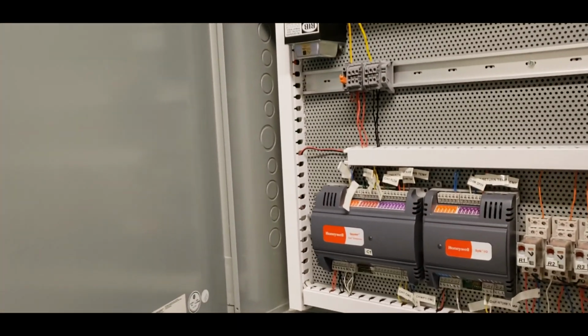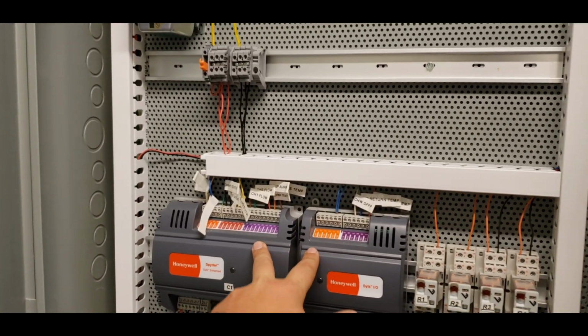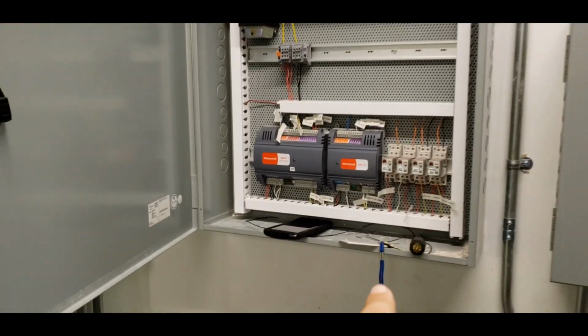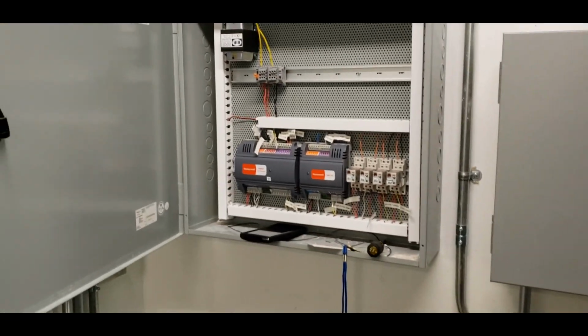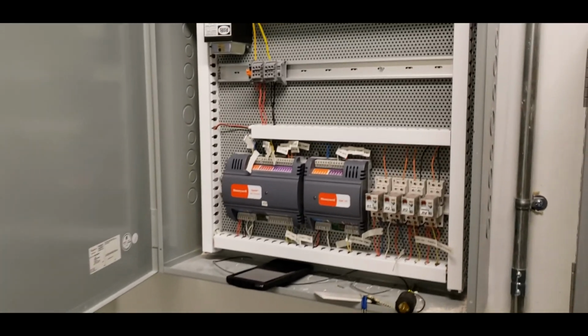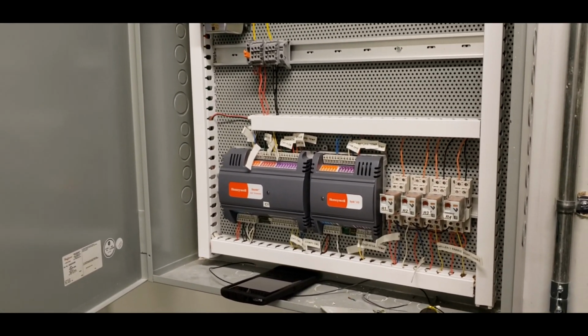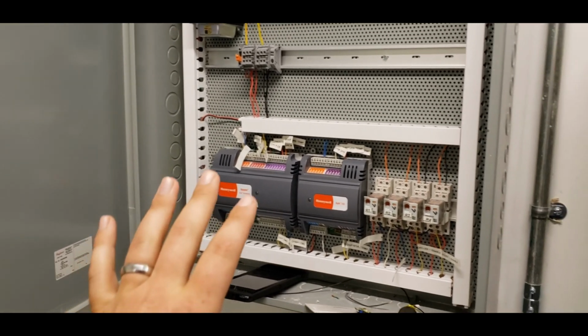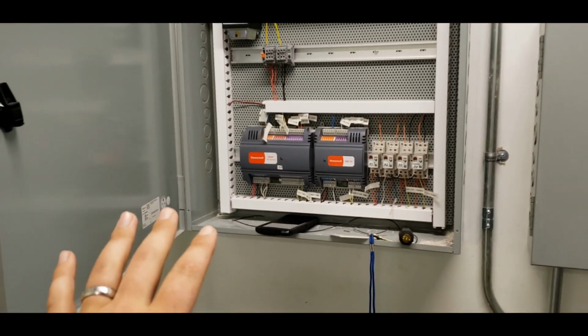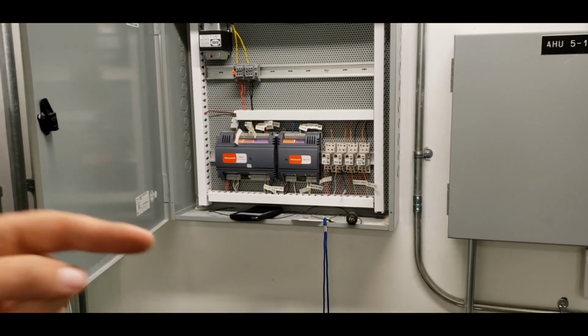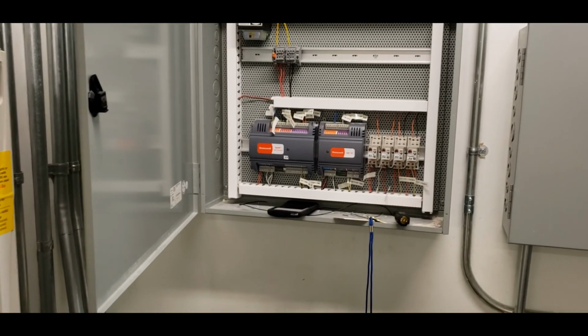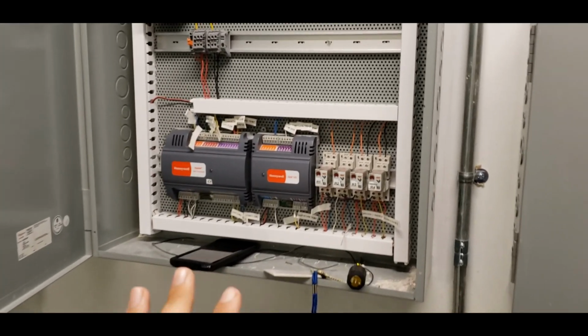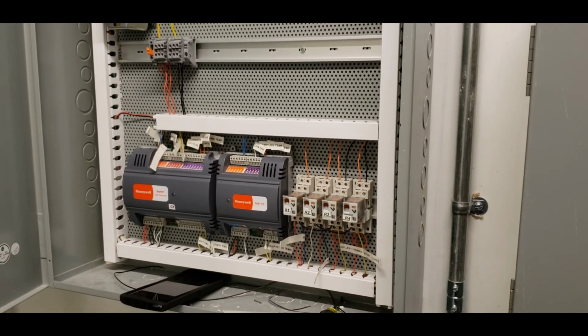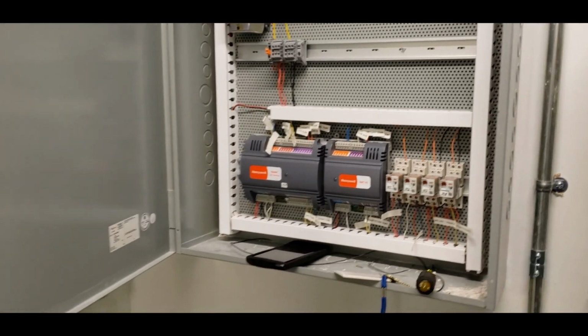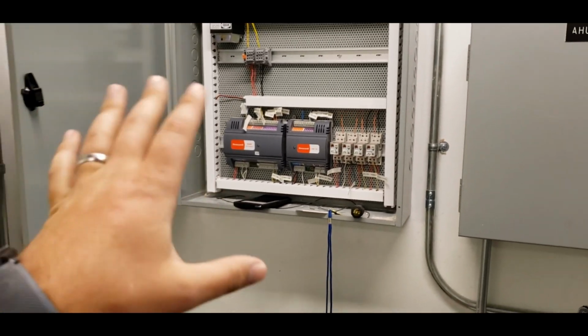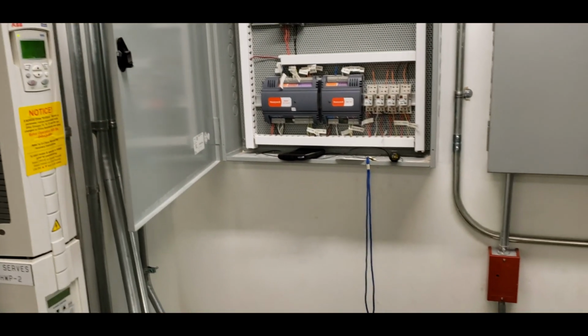Now what I'm left with is I'm trying to get these back online. Since we were troubleshooting and doing the work, now my plant controllers don't want to bring the plant on, because even though they don't have network comms, what they should do is run the preloaded schedule and whatever was in there before it lost comms and started having trouble. It didn't want to do that at first.